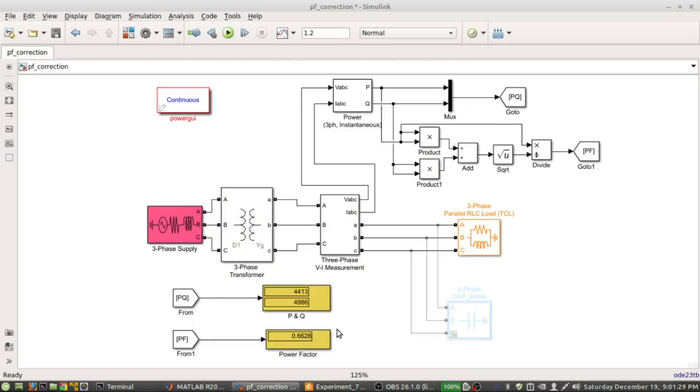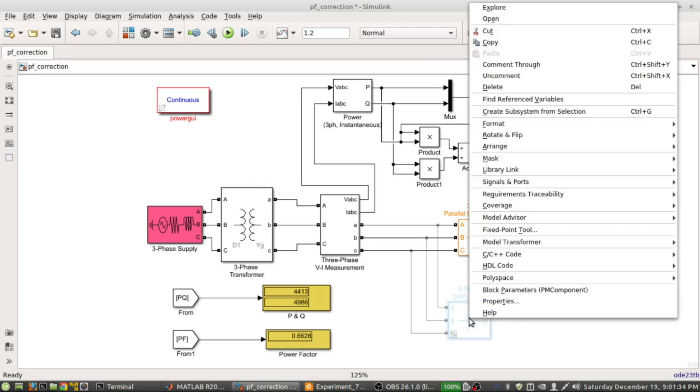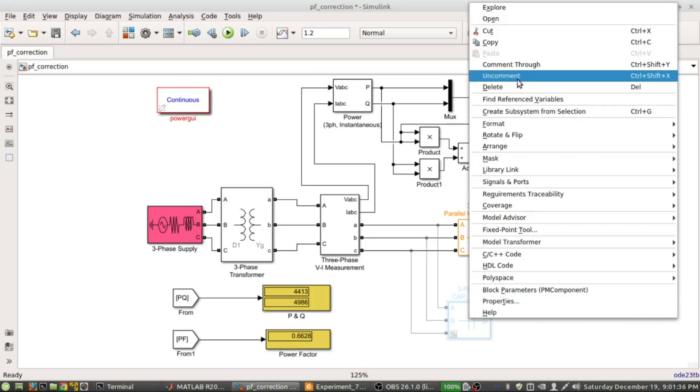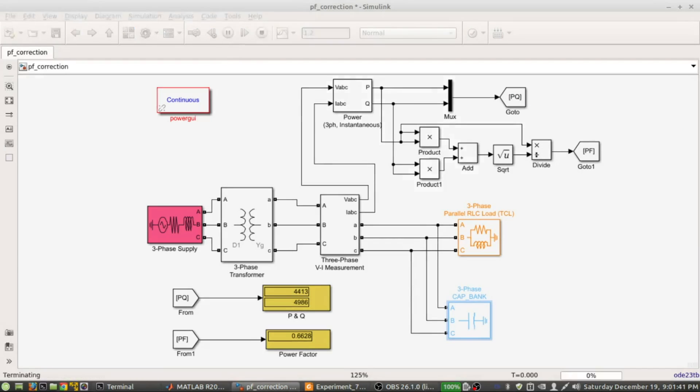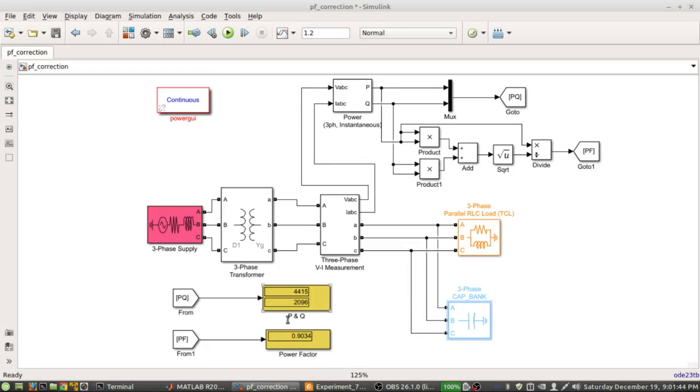Previously our power factor was 0.6628. Now if we use this capacitance bank - that means if I uncomment this, it is now available in the system - now if I run the simulation again, now if you notice the power factor is 0.9034. So we obviously got our desired power factor.